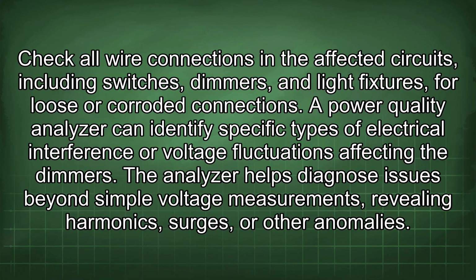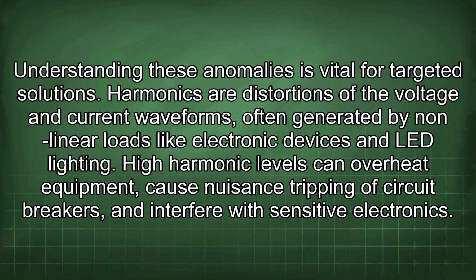A power quality analyzer can identify specific types of electrical interference or voltage fluctuations affecting the dimmers. The analyzer helps diagnose issues beyond simple voltage measurements, revealing harmonics, surges, or other anomalies. Understanding these anomalies is vital for targeted solutions. Harmonics are distortions of the voltage and current waveforms, often generated by nonlinear loads like electronic devices and LED lighting. High harmonic levels can overheat equipment, cause nuisance tripping of circuit breakers, and interfere with sensitive electronics.